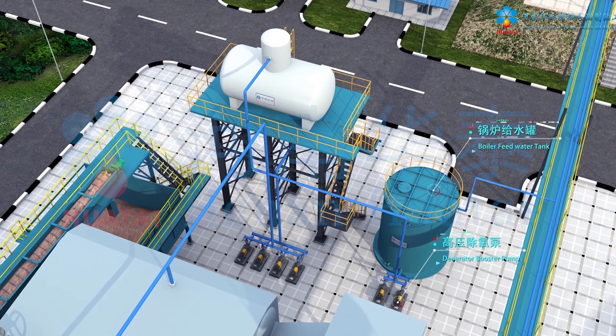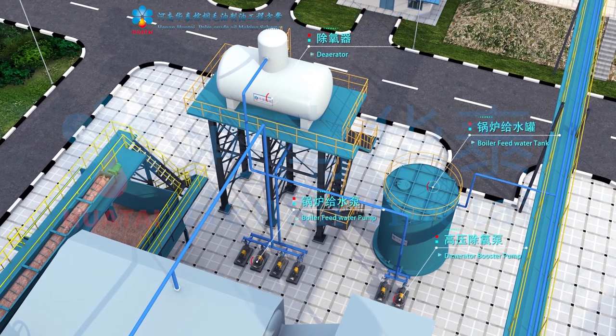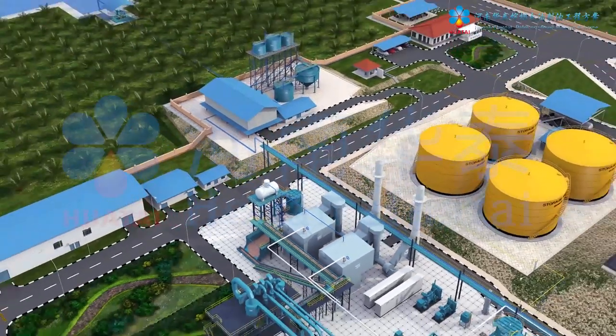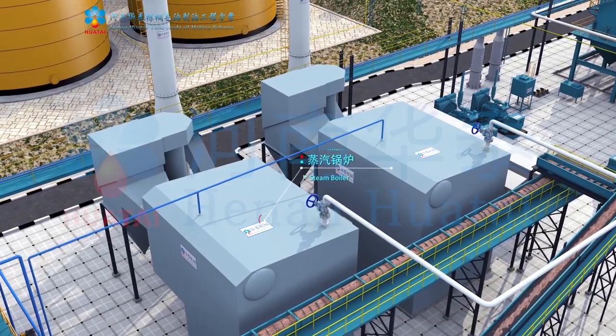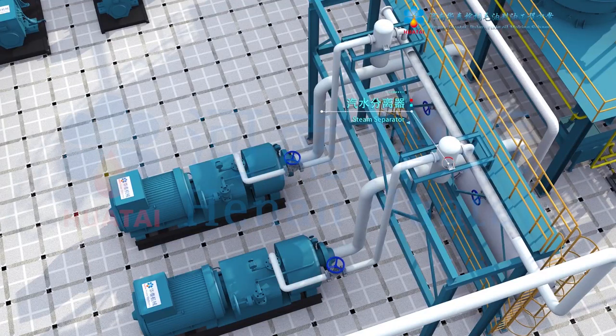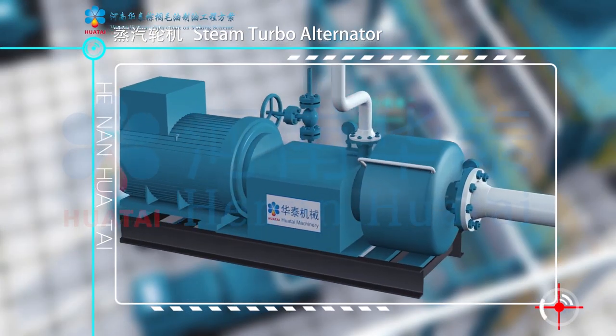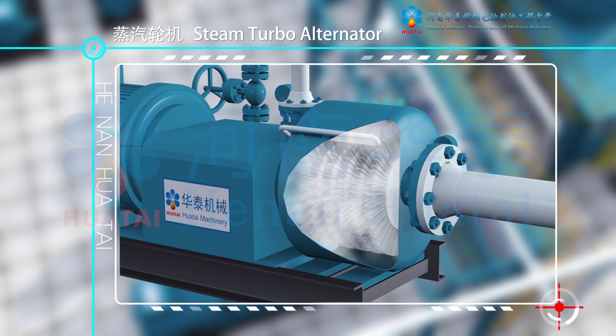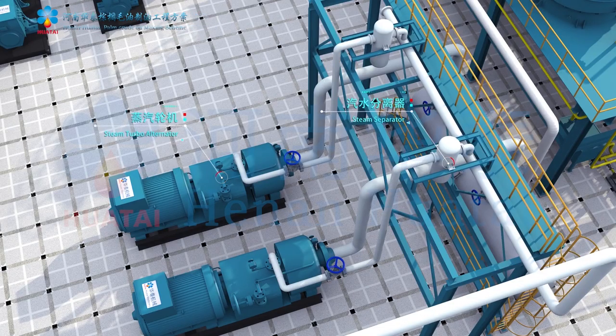Heated water is pumped by the deaerator booster pump to the deaerator. After removing oxygen, water is supplied to the steam boiler and finally pumped to the boiler with the boiler feed water pump. The elevated water tank also supplies water for process production and daily use. The steam boiler is the heat and power source of the whole plant. Through a steam separator, steam moisture is reduced before entering the steam turbo alternator. Under the action of high-pressure, high-temperature steam, the turbo alternator generates high-speed mechanical rotation, converting kinetic energy into electrical energy for plant production and the power grid.